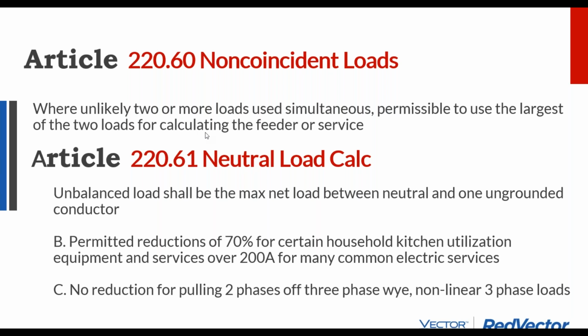And then we get to the neutral load calculation, and sometimes the neutral is allowed to be undersized or eliminated entirely. Neutral loads are kind of the hinge of a seesaw. They're what allows your imbalance between your electric loads from one phase to another to drain without causing power quality issues. 240 volt devices that don't have any other loads on them are perfectly balanced. And so 240 volt devices like some air conditioning units don't even need a neutral. So based on what the exact application is, you can eliminate the neutral entirely for 240 volt devices. And then sometimes you're allowed to undersize it.